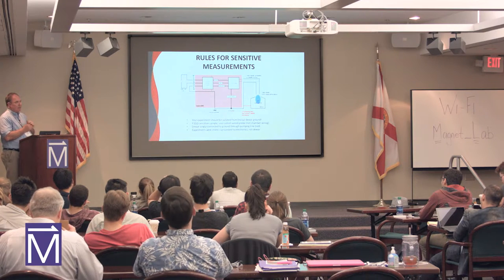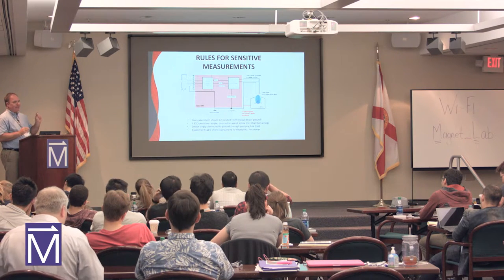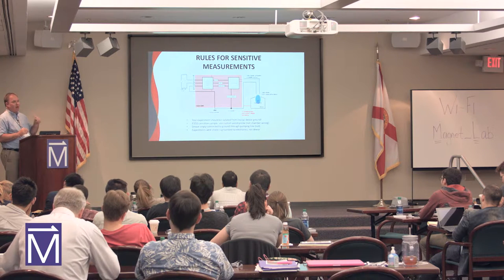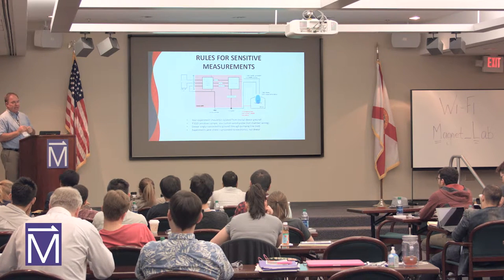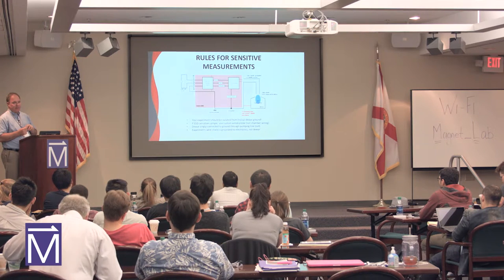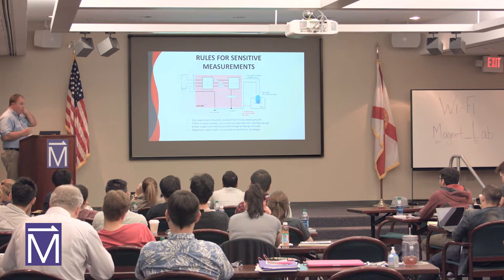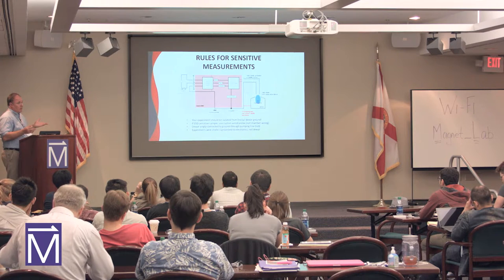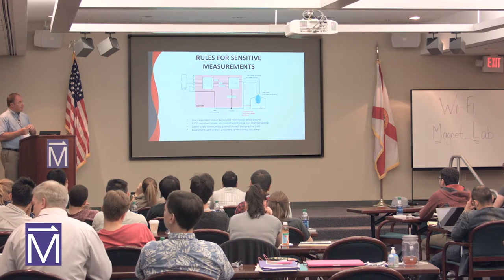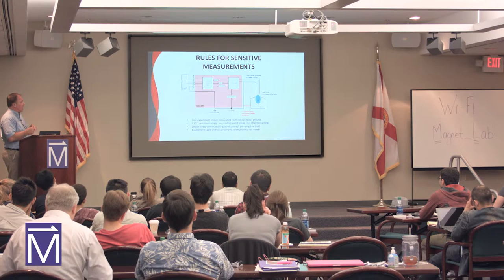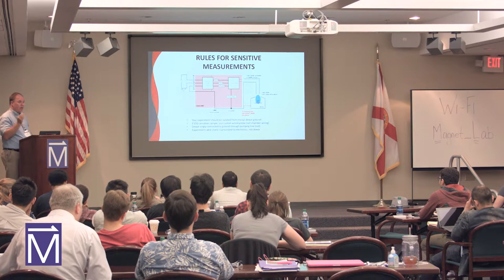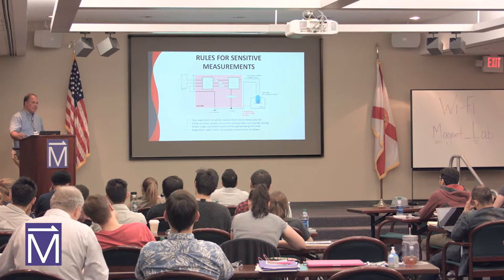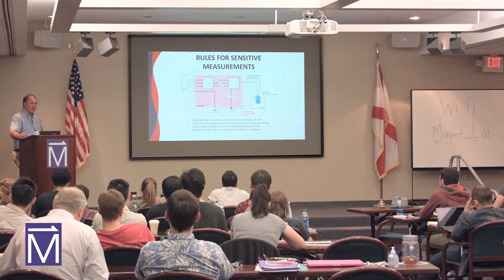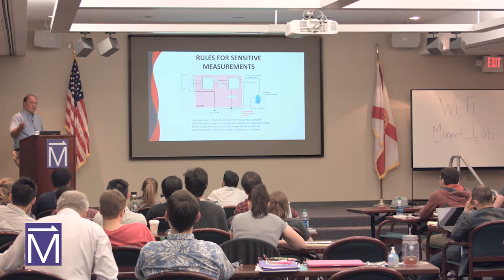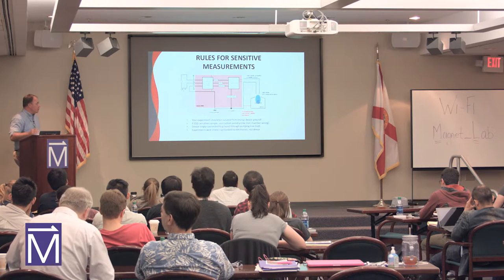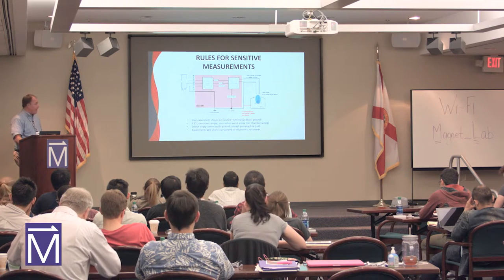ESD sensitive sample. So here's the case where everything that I've talked to you about the pucks goes out the window. You need to make your own probe and run your own wires down to the probe if you have those samples. And it's due to the way that the ground in the system is. So you have to take care of this case. When we have customers that have ESD sensitive samples, we recommend that they design their own type of probe for that. So we have some solutions for that, and we have some solutions coming up for that.